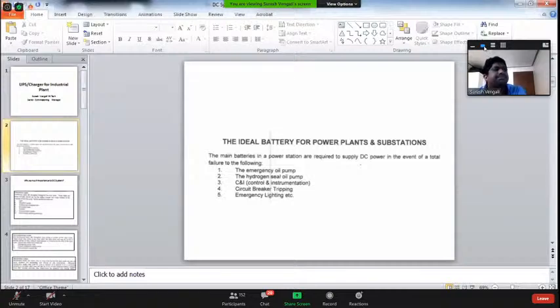Let me explain where we use it. As you've already seen in substation control systems, you need a supply, your protection relay needs a supply, emergency lighting needs a supply, and circuit breaker tripping needs a supply. All these things, like the emergency lighting I mentioned, you may take from the battery source or DC bus, or you may have internal batteries for that. I'm not talking about internal batteries here, only about feeding from the DC bus. So these are the areas where you regularly need a DC supply.